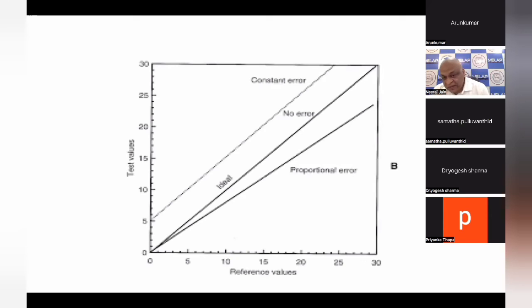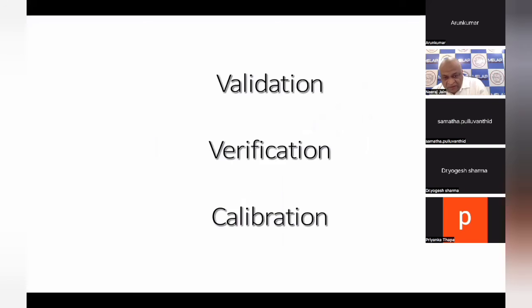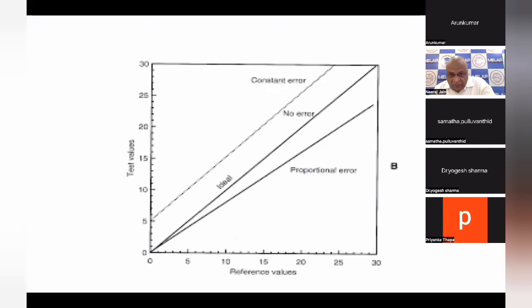is regression analysis. Results on the old machine on the x-axis, results on the new machine on the y-axis. Hemoglobin on the old machine is 5, it should be close to 5 on the new machine. Results on the old machine 10, on the new machine also it should be close to 10 only. Then you will get a line at 45 degrees. This is an ideal situation.